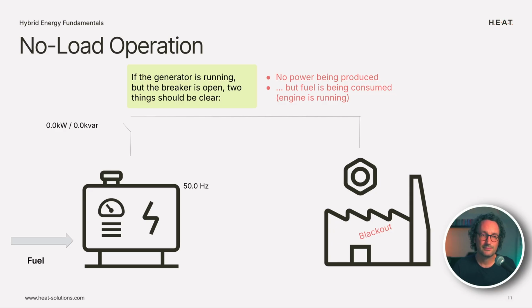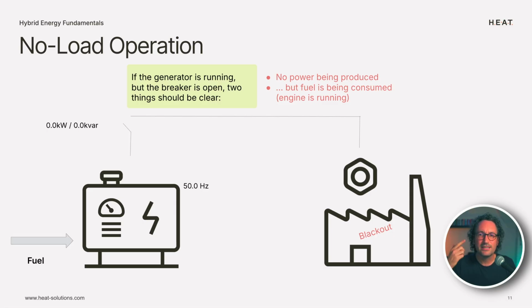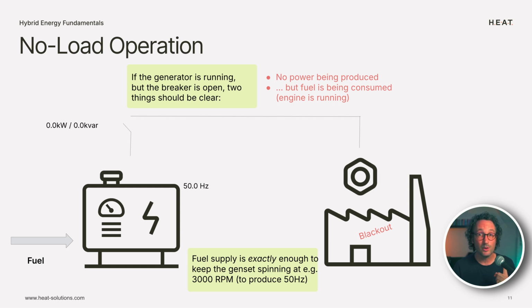Let's dive a little bit deeper. And I want you to imagine for a second that we've got a blackout on our island. The diesel generator is on, it's running, but the breaker at its output is open. And this means that there is no power being supplied to the factory, and there's a blackout. So we can tell that since the generator's running, we can hear it turning over, and there's smoke coming out of it. So obviously it's consuming some fuel, but it's not producing any power. And the reason for that is that the fuel supply to the generator in this moment is exactly enough to keep the genset spinning at, for example, 3,000 RPM. 3,000 RPM for certain gensets will produce exactly 50 hertz in the frequency of the output power. And that's what we want. We want 50 hertz. So we found the exact fuel rate that spins our engine at that speed.